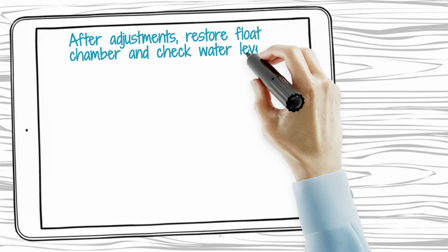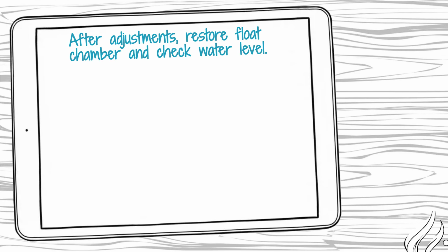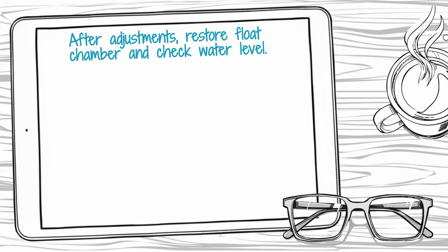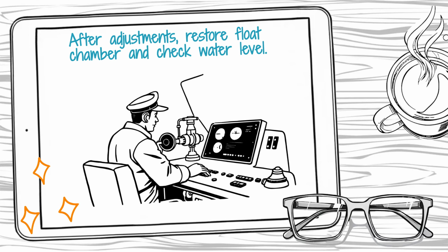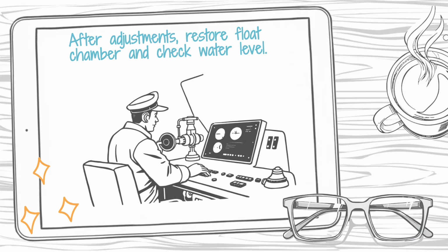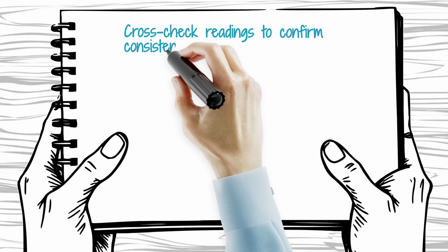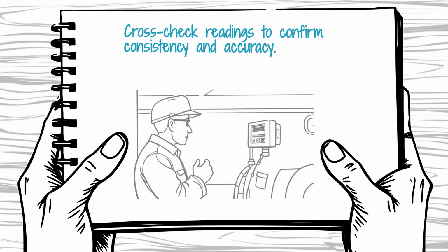After the set points are verified and adjusted if necessary, close the drain valve and slowly open the water and steam balance valves to return the float chamber to service. Observe the level as it rises back to the normal operating position and ensure the alarms clear automatically. Perform a final check by cross-referencing the local gauge glass reading with the remote indicator to ensure there is no deviation in the signal.